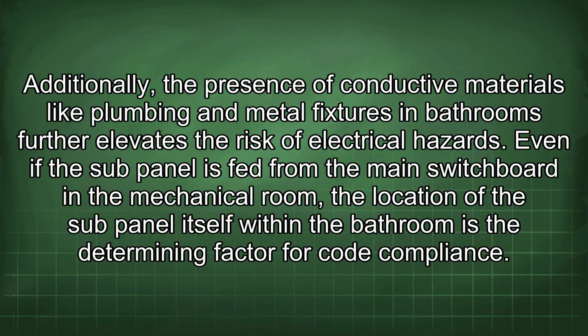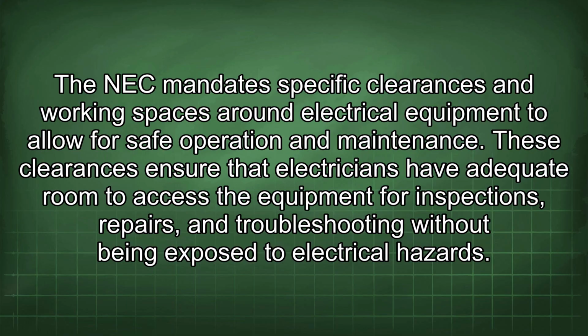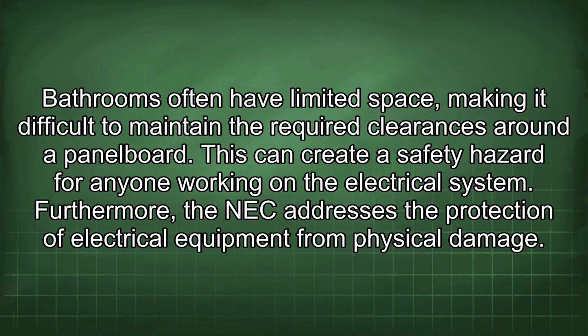Even if the subpanel is fed from the main switchboard in the mechanical room, the location of the subpanel itself within the bathroom is the determining factor for code compliance. The NEC mandates specific clearances and working spaces around electrical equipment to allow for safe operation and maintenance. These clearances ensure that electricians have adequate room to access the equipment for inspections, repairs, and troubleshooting without being exposed to electrical hazards. Bathrooms often have limited space, making it difficult to maintain the required clearances around a panel board. This can create a safety hazard for anyone working on the electrical system.